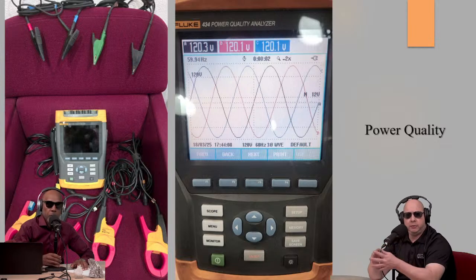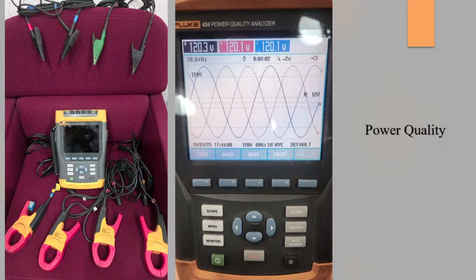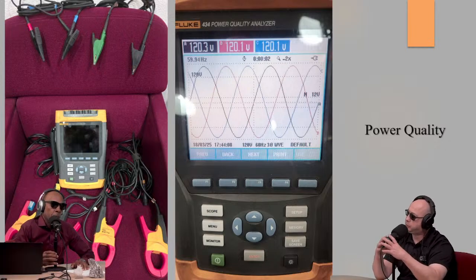The top clamps monitor your voltage coming into or out of your system, and the amp clamps at the bottom monitor your current. The alligator clips on top are put on the terminals of the output power from the unit, or the input power to the load bank, since it's the same thing - on the terminal lugs for the power. The bottom ones clamp around the cables or conductors to get the amperage. So simplified: the alligator clips are at the top, and the amp clamps are at the bottom, broken down in layman's terms.